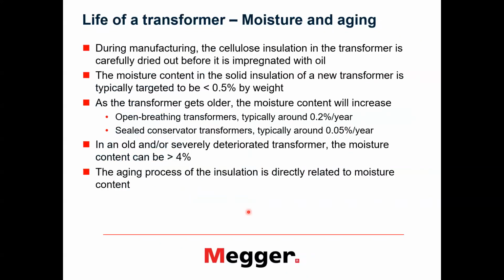During manufacturing, the cellulose insulation of the transformer is dried out before it's impregnated, and when it's a new transformer, the moisture content is lowered as much as possible so that it's below 0.5% by weight. But as the transformer gets older, the moisture content in it increases. If it is an open breathing transformer, it will be like 0.2% a year, which is quite a lot. But most of the transformers are sealed, so there will be like 0.05% a year, which is not that much, but over several years it will accumulate.